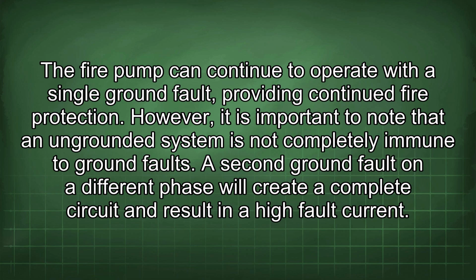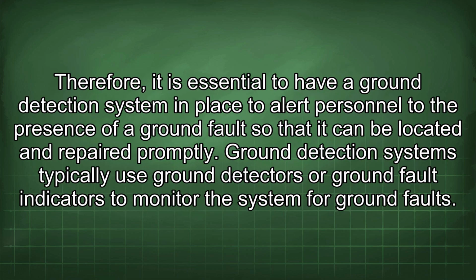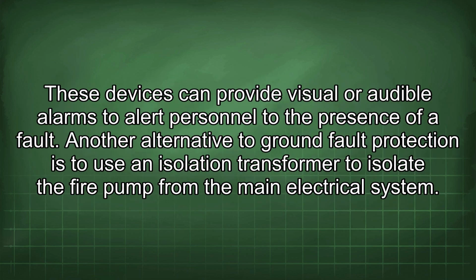However, it is important to note that an ungrounded system is not completely immune to ground faults. A second ground fault on a different phase will create a complete circuit and result in a high fault current. Therefore, it is essential to have a ground detection system in place to alert personnel to the presence of a ground fault so that it can be located and repaired promptly. Ground detection systems typically use ground detectors or ground fault indicators to monitor the system for ground faults. These devices can provide visual or audible alarms to alert personnel to the presence of a fault.